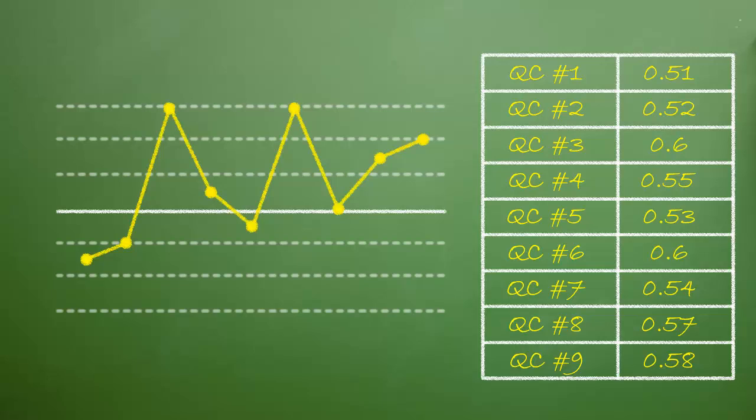This verification occurs by comparing daily QC results to lab-defined ranges of QC values. There's a number of ways to determine if a control is acceptable. The most common approach is Westgard rules. If you're interested, check out our Blackboard videos on Westgard rules.